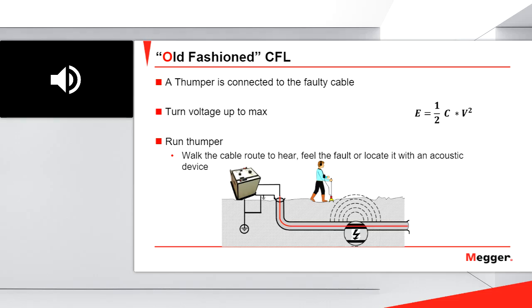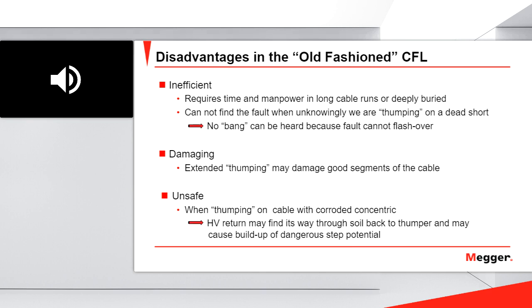Okay, so this is a disadvantage, because maybe the breakdown voltage of my fault is only 2 or 3 kV, but since I need to hear the fault, maybe I can go up to 25 or maybe up to 32 kV in order to hear it. But this is not the only disadvantage. There are many, many disadvantages with the old-fashioned cable fault location method or process. It is inefficient, as I mentioned, because with long cables this method requires time and manpower in long cable runs.